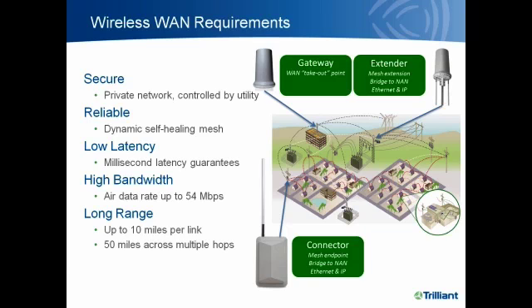Technology from Trilliant can provide links up to 10 miles apart and can hop over multiple links. For example, across five hops you can extend coverage out across 50 miles. There are a couple of different components of this Wireless WAN. The gateway is a device that provides the start of a Wireless WAN network that connects to a wired backhaul network. The extender takes the Wireless WAN and extends it over multiple hops of a mesh network. The connector provides an endpoint on the Wireless WAN mesh.